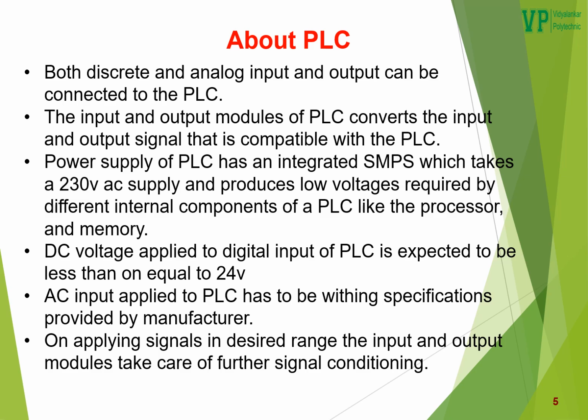The power supply of a PLC has an integrated SMPS which takes a 230 volt AC supply and produces the low voltages required by different internal components of the PLC, like the processor, memory, and other system components. DC voltage applied to the digital input of a PLC is expected to be less than or equal to 24 volt DC. The AC input applied to the PLC has to be within the specifications provided by the manufacturer. On applying signals in the desired range, the input and output modules take care of further signal conditioning, thereby avoiding extra signal conditioning.